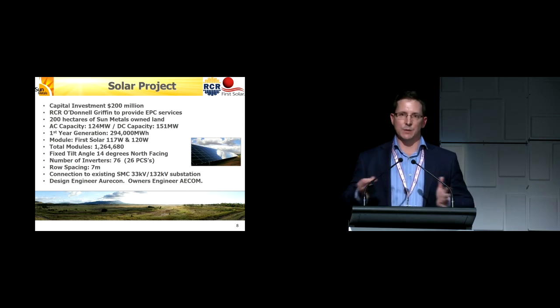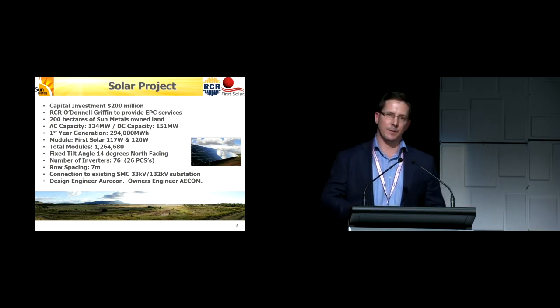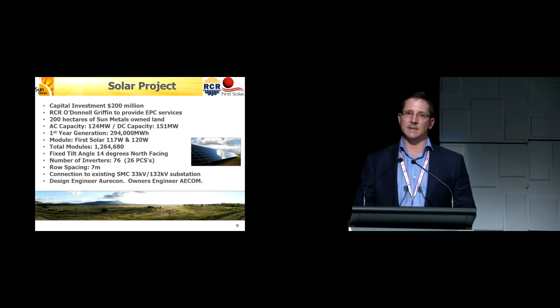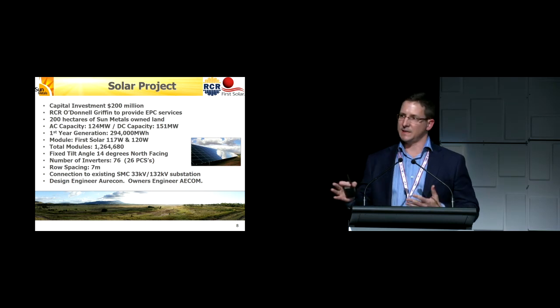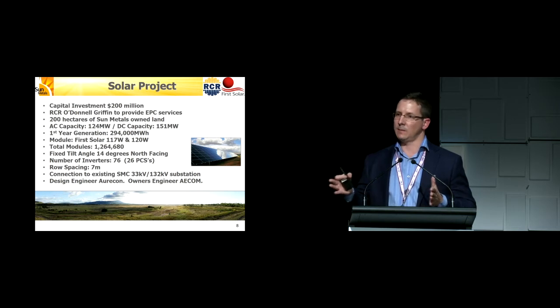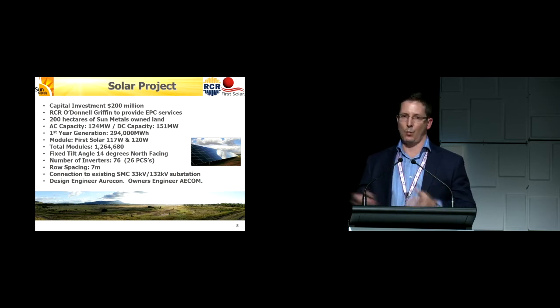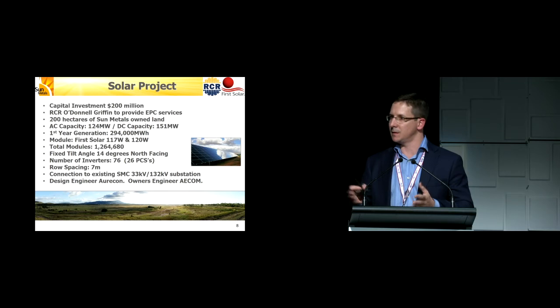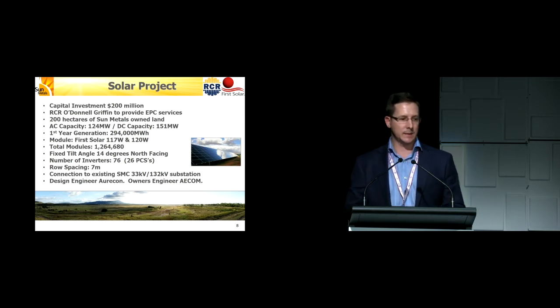The spacing between rows - the design is a fixed tilt system, 14 degree tilt facing north, fixed angle. Spacing between rows is about 7 metres from the centre of one row to the next, and distance between rows, from the end of one row to the next, is only about 2 metres.